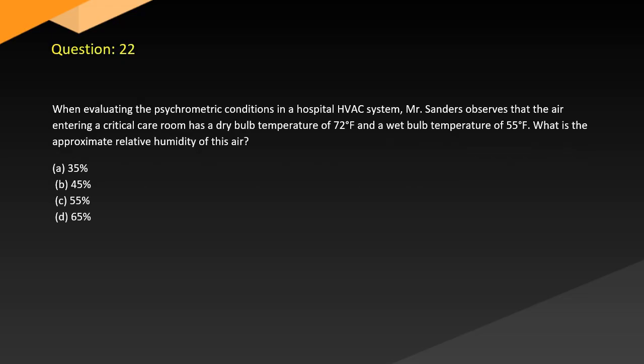Question 22. When evaluating the psychrometric conditions in a hospital HVAC system, Mr. Sanders observes that the air entering a critical care room has a dry bulb temperature of 72 degrees and wet bulb temperature of 55 degrees. What is the approximate relative humidity of this air? A. 35%, B. 45%, C. 55%, D. 65%.